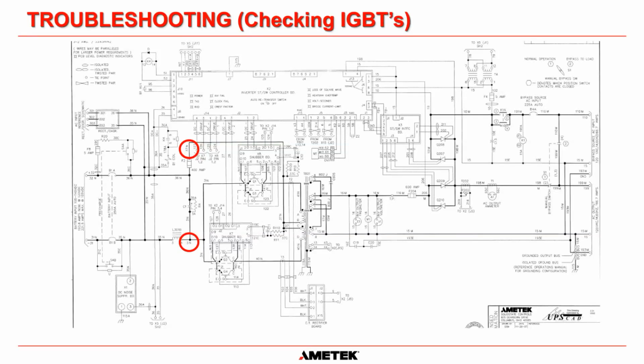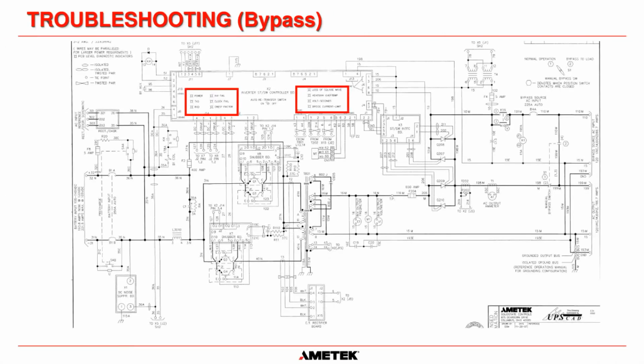Okay. I know it's a lot of information. You can go back and watch it on YouTube and pause it and think about it. But that's if the inverter is not running. Now, if the inverter is on bypass, then the control board has some handy LEDs. So you have to open the door and look on the back of the X2 inverter static switch controller. And there are some good LEDs that can tell you something about what has gone on within the system itself.